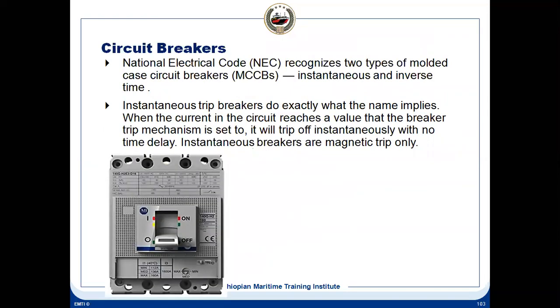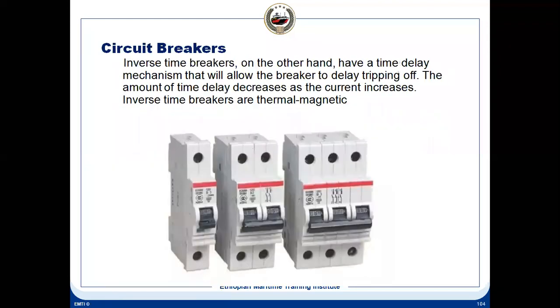Circuit breakers. There are 2 types of circuit breakers we will discuss here. What is instantaneous and inverse time? You see, instantaneous circuit breakers do exactly what the name says. Instantaneous means immediate. When the current in the circuit breaker reaches a value that the breaker trip mechanism is set for, it will trip immediately. No time delay. That is known as an instantaneous breaker. So the NEC recognizes 2 types of breakers: instantaneous type breakers and inverse time breakers.